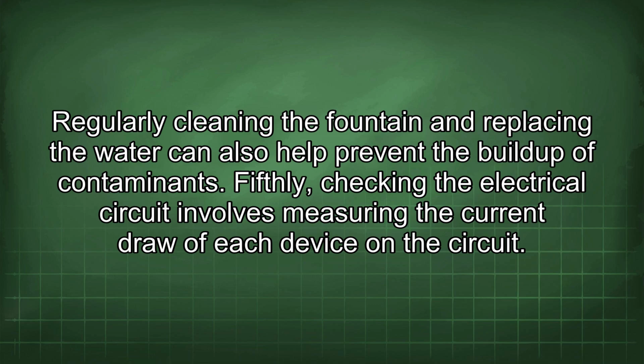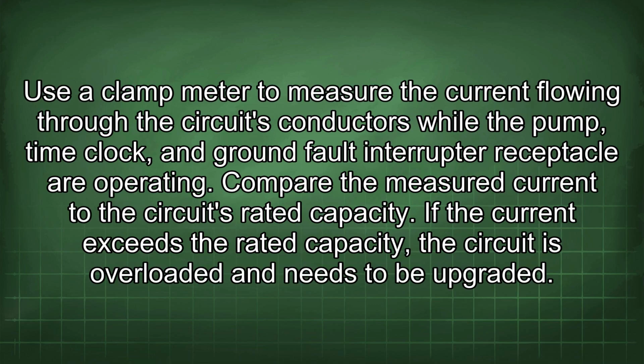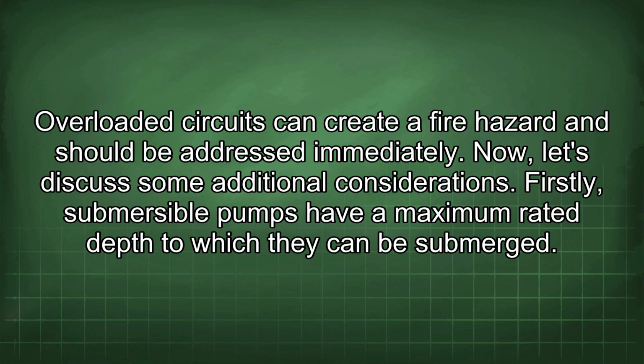Fifthly, checking the electrical circuit involves measuring the current draw of each device in the circuit. Use a clamp meter to measure the current flowing through the circuit's conductors while the pump, time clock, and ground fault interrupter receptacle are operating. Compare the measured current to the circuit's rated capacity. If the current exceeds the rated capacity, the circuit is overloaded and needs to be upgraded. Overloaded circuits can create a fire hazard and should be addressed immediately.